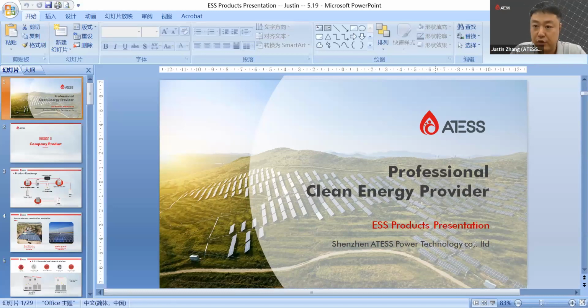The parallel number is up to 4 units, meaning all of our PCS units can work alone or in parallel up to 4 units. So if we choose the PCS 630 kilowatt times 4, doing a simple calculation, we can reach up to 2.5 megawatts.